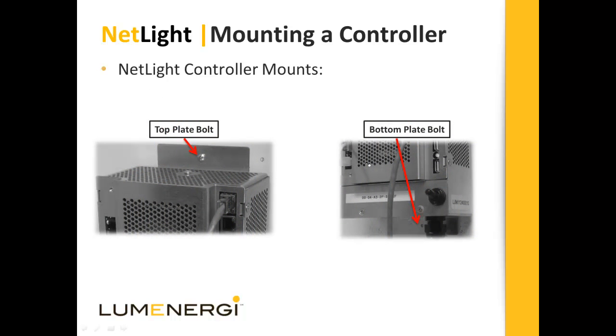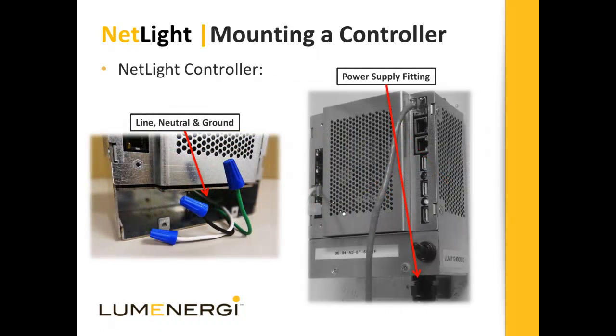To mount the NetLight controller, use appropriate size bolts to secure the unit using the top and bottom mounting plates. To provide power to the NetLight controller, first you must remove one of the 3 punch outs located underneath the unit and also detach the lower front plate by unscrewing the bolts. Next, run a power line through the punch out and hardwire the line, neutral, and ground wires to the capped wires inside. Reattach the lower front plate and hardwire the power line into a nearby power outlet. LED indicators will show the controller has power.